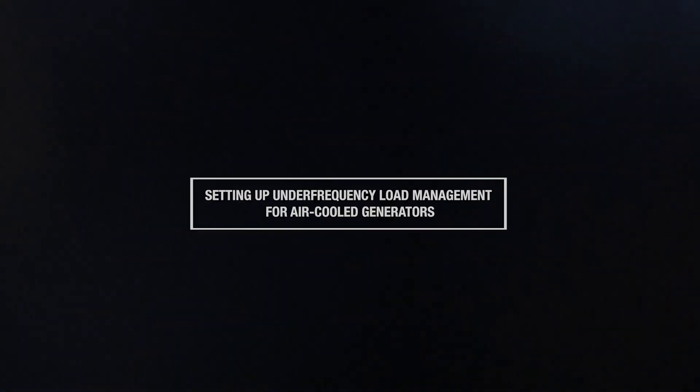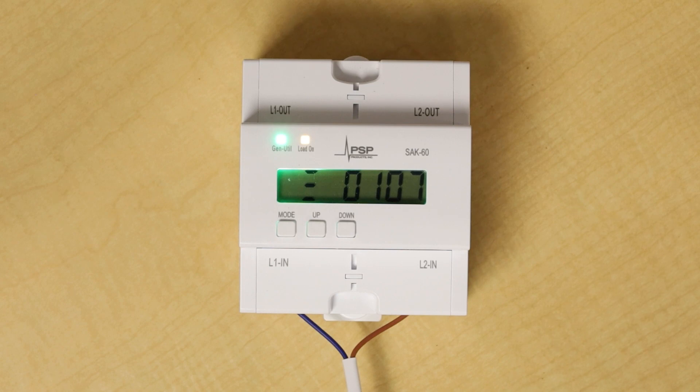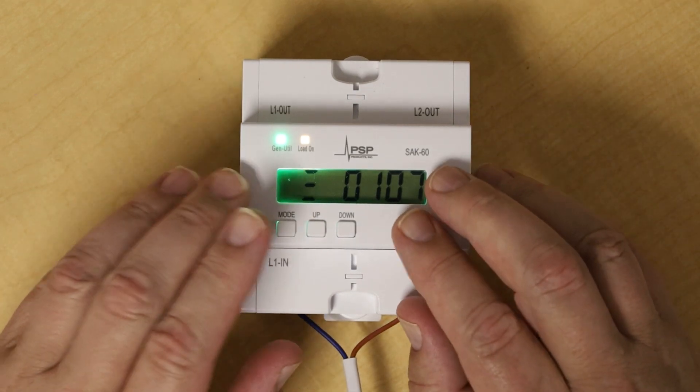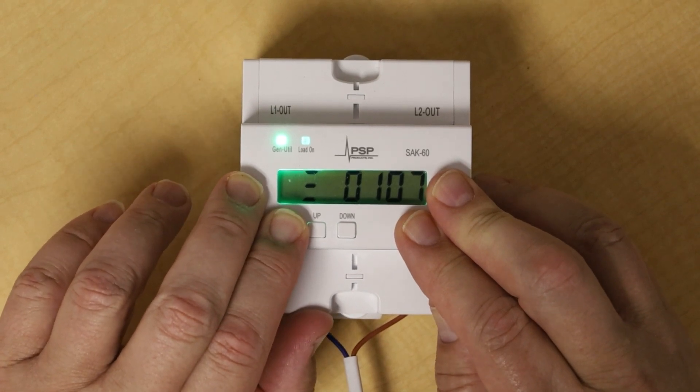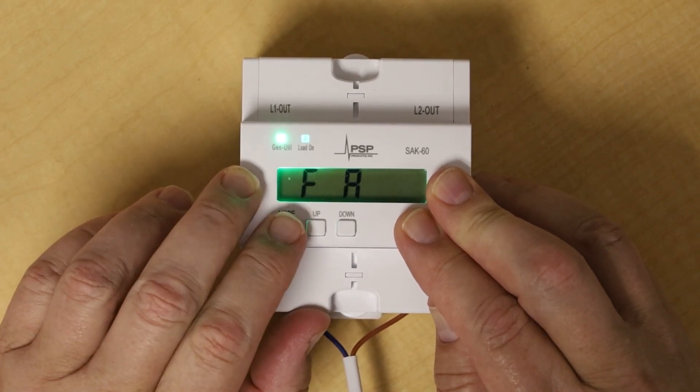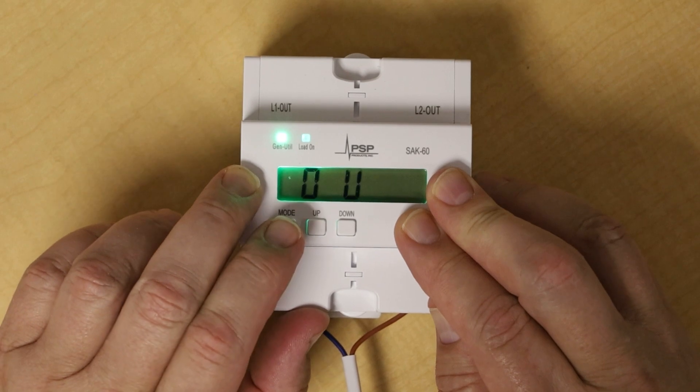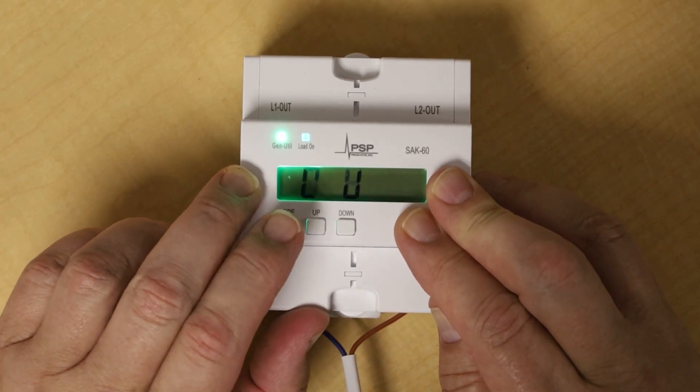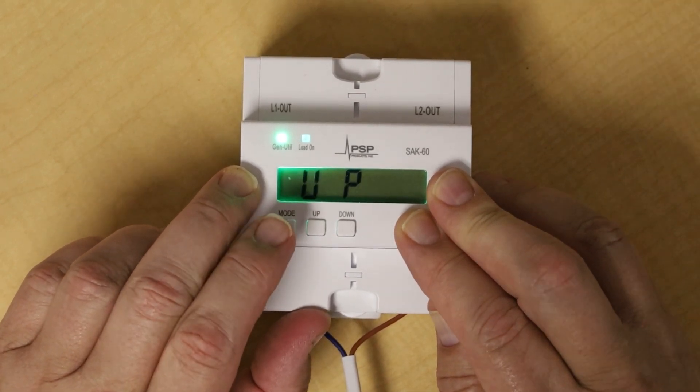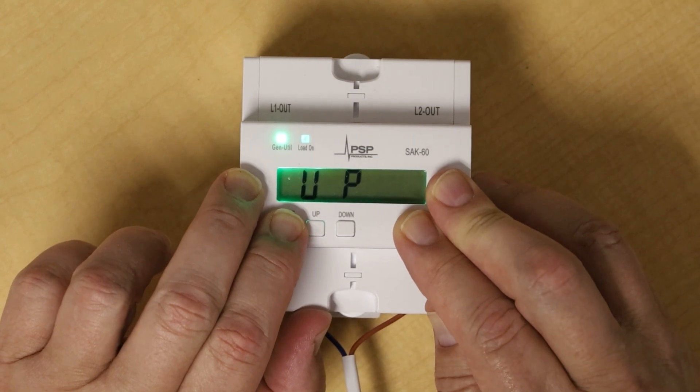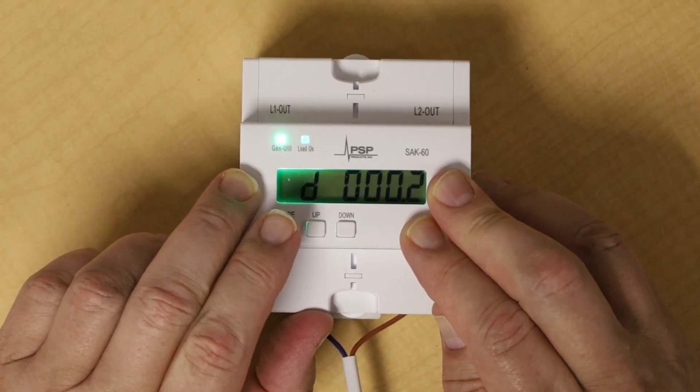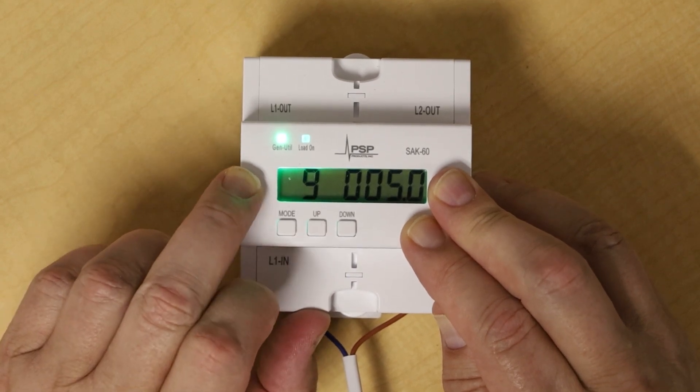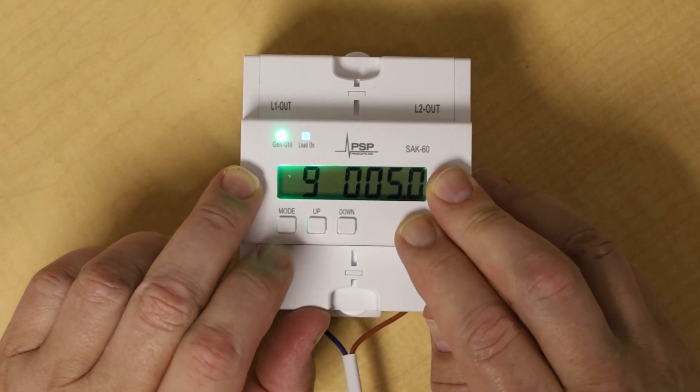To set up the SAK60 version 3 for under frequency load management with an air-cooled generator, first hold the mode button for 3 seconds until 2 digits appear. Press the mode button briefly to scroll to UP. Hold the mode button to enter programming mode. The first setting does not need adjustment. Press the mode button again to scroll to G, which looks like a 9—it's a lowercase g.